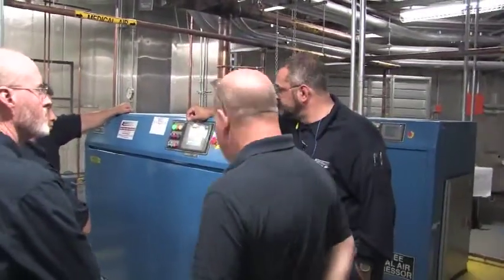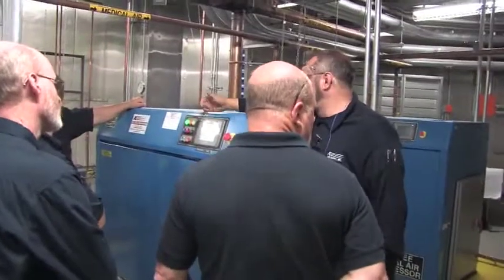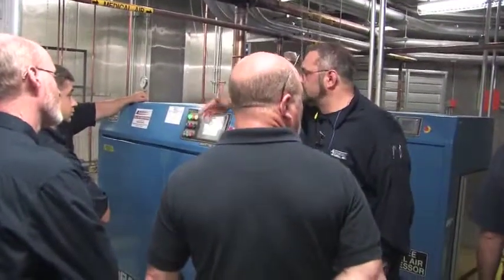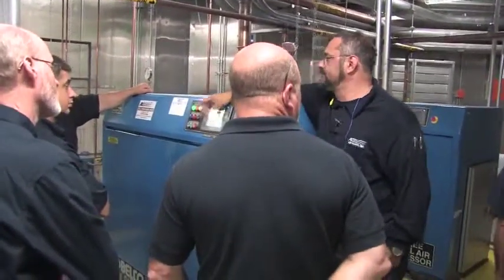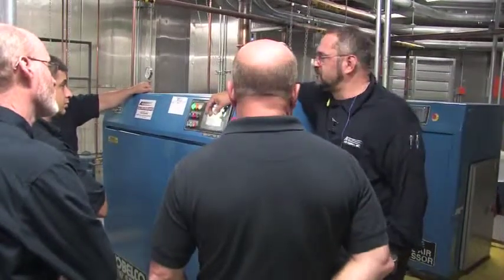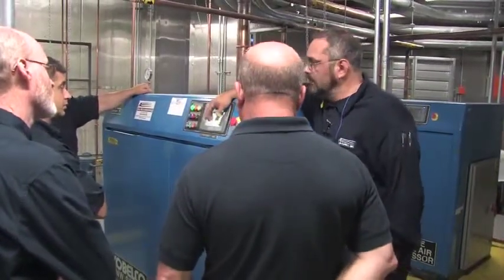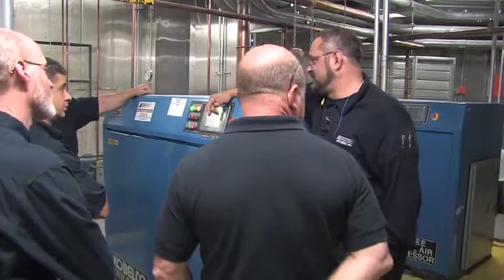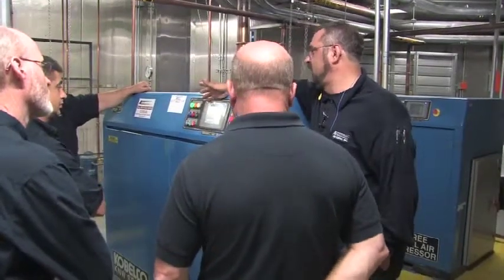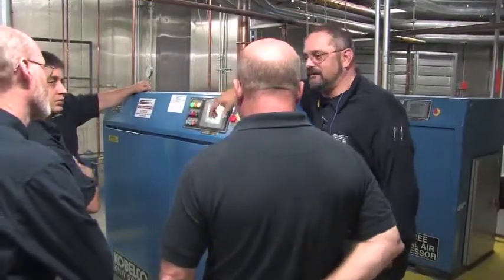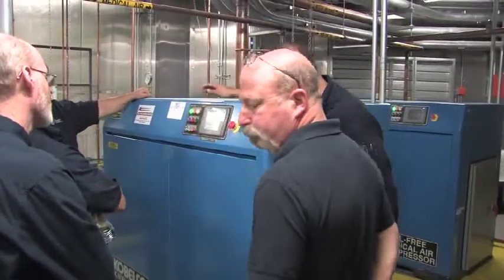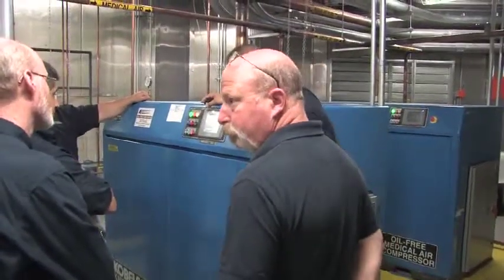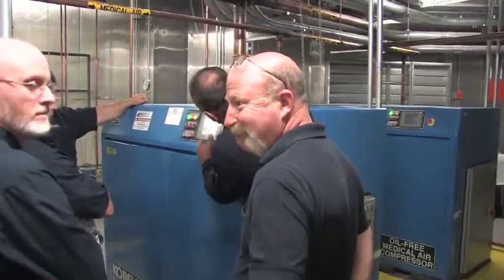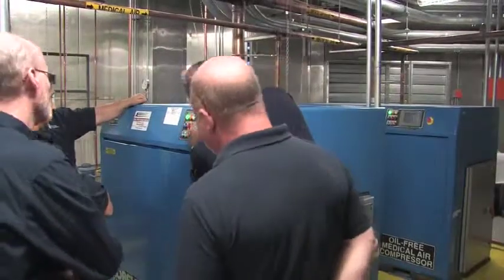Only on the intercooler. The other two are by hand. And there's a hand valve on that one too, but you pretty much set it and let it go, unless it's running too cold. But then the right thing to do is to adjust the regulator rather than just throttle a hand valve. But you're taking the regulator out, it just has to go. Exactly. Some of the biggest differences.